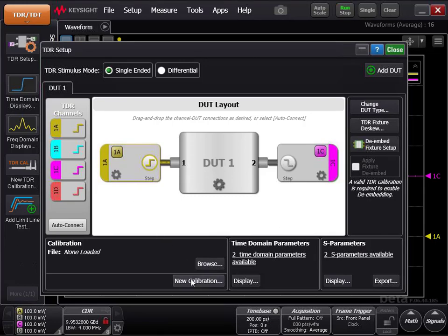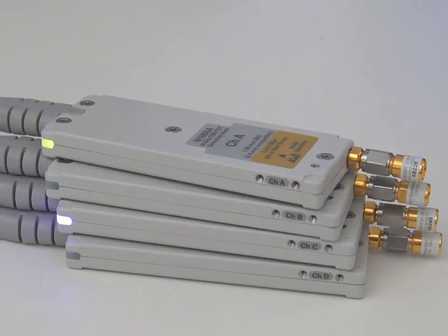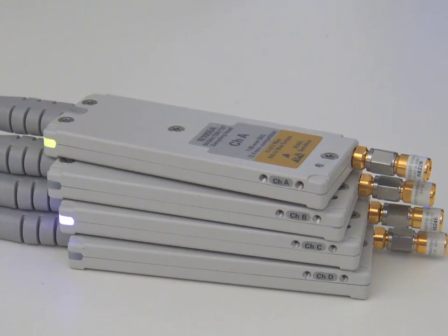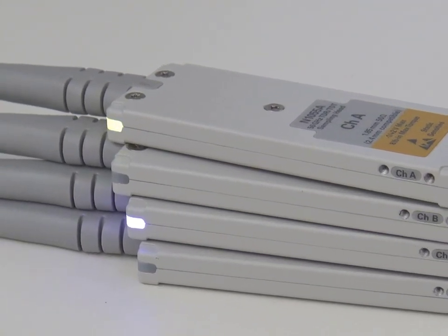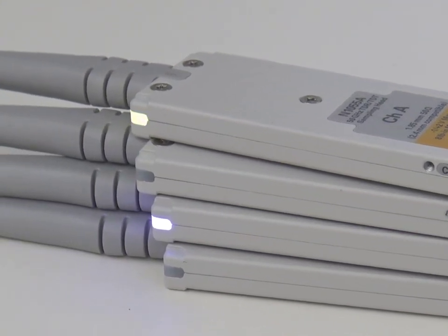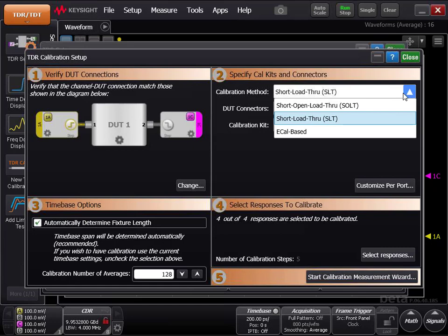In the calibration area, click New Calibration. Separate the channels you are using from the channels you are not using. An easy way to do this is to look at the status light on the bottom corner of the measurement heads. The ones you will be using are illuminated. In area number 2, specify CAL kits and connectors. Under calibration method, select ECAL based.